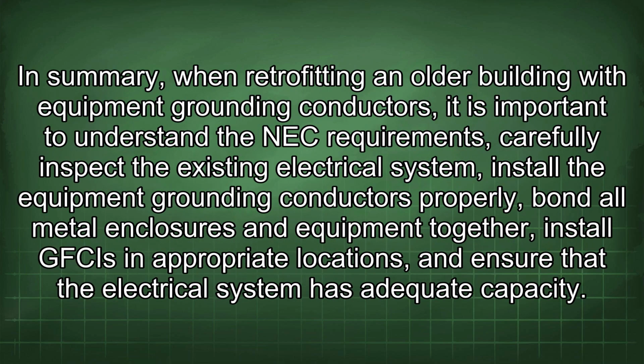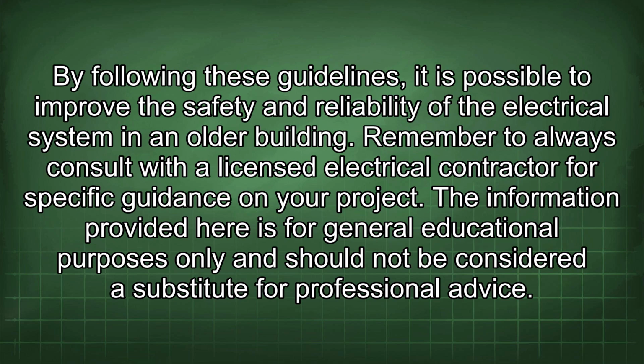In summary, when retrofitting an older building with equipment grounding conductors, it is important to understand the NEC requirements, carefully inspect the existing electrical system, install the equipment grounding conductors properly, bond all metal enclosures and equipment together, install GFCIs in appropriate locations, and ensure that the electrical system has adequate capacity. By following these guidelines, it is possible to improve the safety and reliability of the electrical system in an older building. Remember to always consult with a licensed electrical contractor for specific guidance on your project. The information provided here is for general educational purposes only and should not be considered a substitute for professional advice.